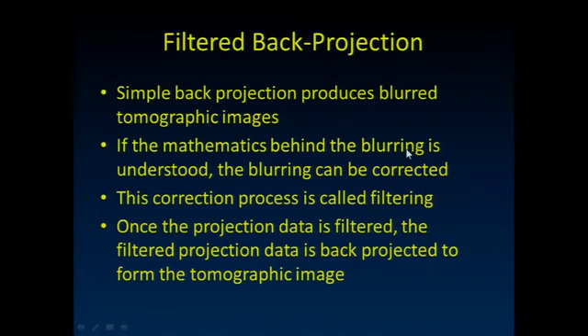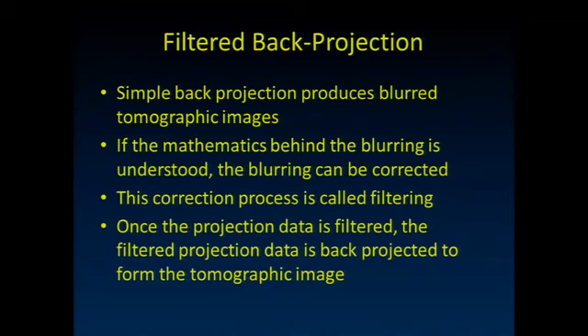So how do we correct for that? Simple back projection basically produces a blurred slice image of the true object. If we can understand the mathematical process behind the blurring, we can correct for it—and that's exactly what filtering does. Filtering is the correction applied so that when you do the back projection, the image turns out looking correct. So: filtered back projection. We filter those projections and then do the same back projection.